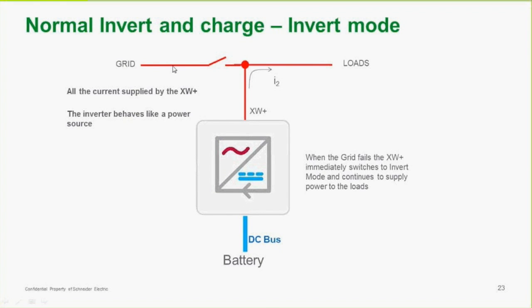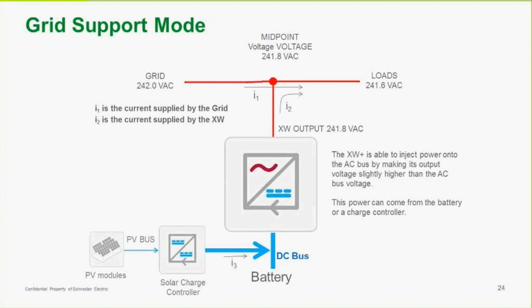If the grid becomes disconnected and our batteries are charged up, then the inverter basically provides power from the battery, inverts it into AC, and supports the loads. So now the inverter looks like it's a power source. In grid support mode, the inverter's injecting power onto the AC bus. What it does is it increases its AC voltage a little bit and adds to the voltage being supplied by the grid.